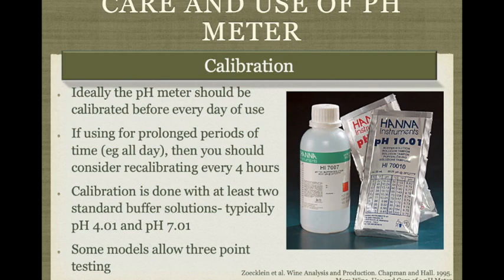If you're going to use it all day long, it's probably best to calibrate it every 4 hours. And usually we do two-point calibration with standardized buffer solutions, typically 4.01 and a pH of 7.01. There are some models that actually allow 3-point calibration testing.